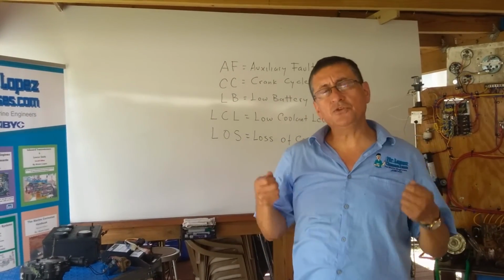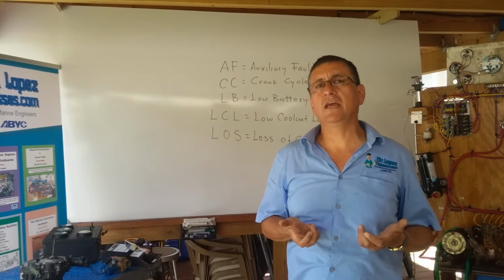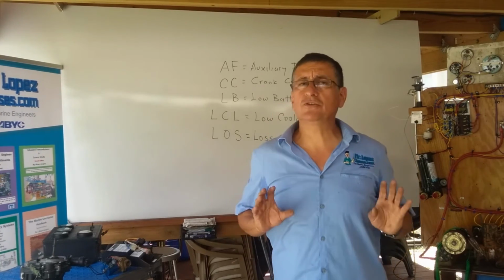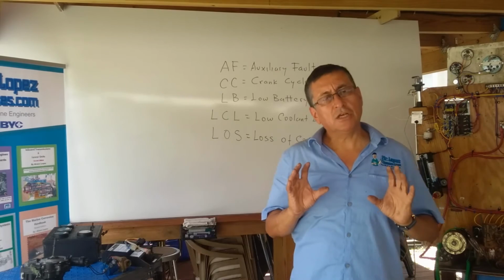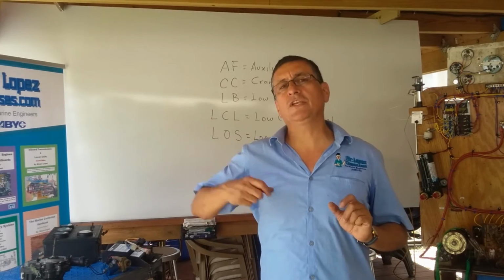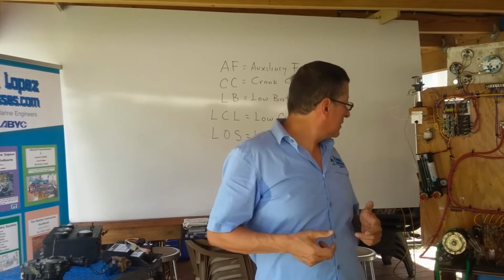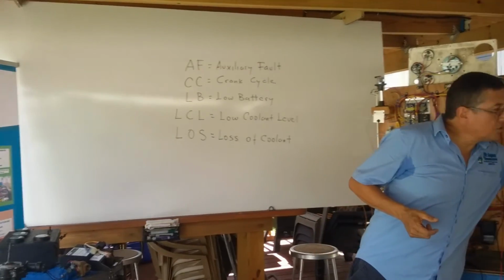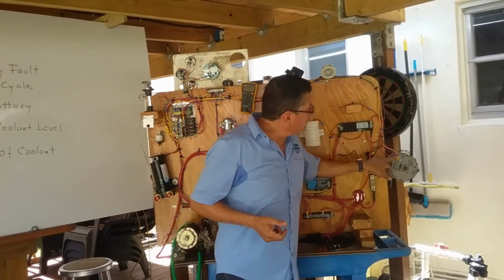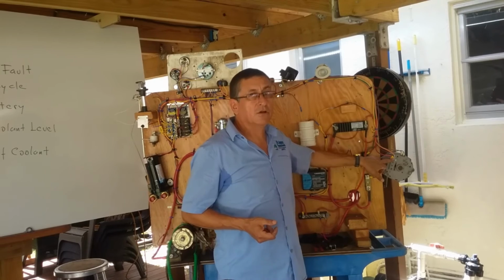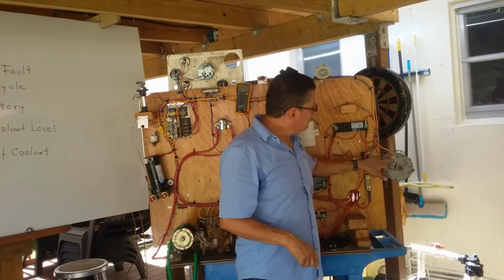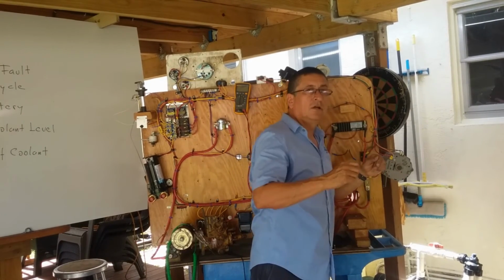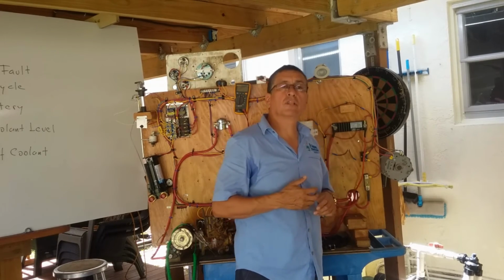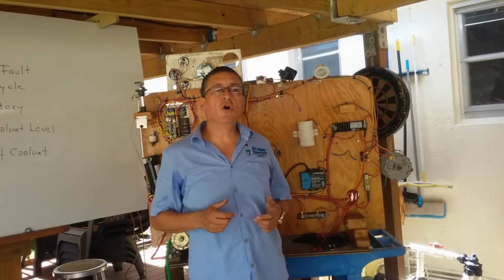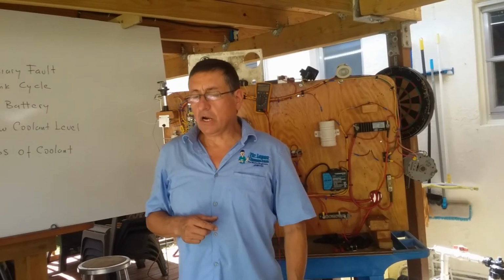With the load tester, you check the condition of the batteries and verify if the battery is okay. Be careful, because in some cases the battery is good but the problem is the alternator of the generator. The alternator doesn't send the charge properly. You need to verify at the output of the alternator, when the engine is running, if the alternator produces more than 13.2 volts DC.